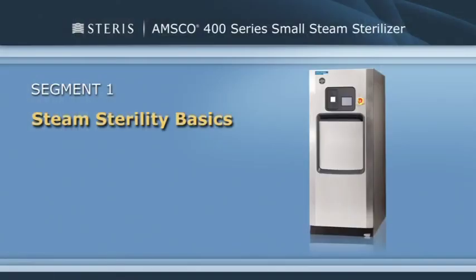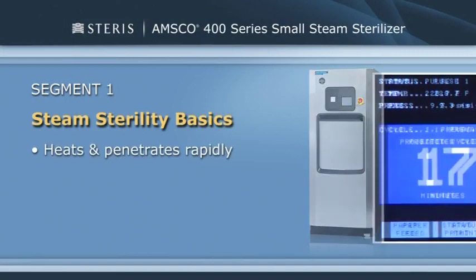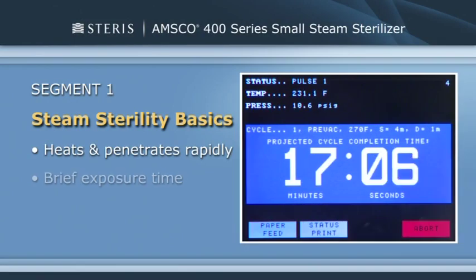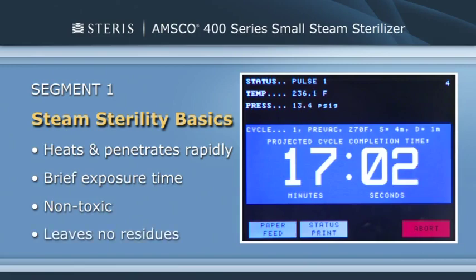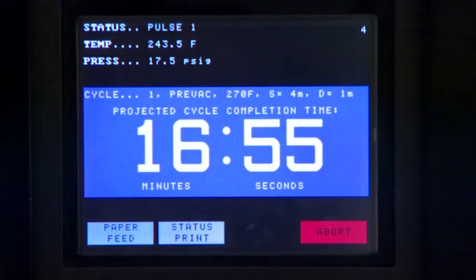Steam sterilization is the most cost-effective and dependable sterilization method available for surgical instrumentation. Steam heats and penetrates rapidly, requires brief exposure time, is non-toxic, and leaves no residues. Because of the high temperatures generated during this process, surgical instruments that are heat and moisture sensitive cannot be sterilized with steam. Please refer to all manufacturer recommendations on sterilization before processing surgical instrumentation.